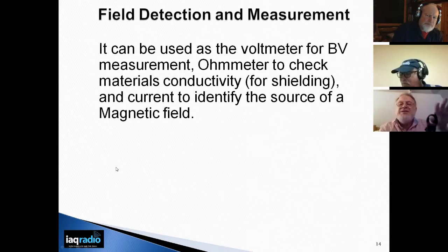So we took the meter, connected leads, and checked the electrical resistance of the screening, and the screen was definitely plastic, not metallic. Being plastic, it was of no use for shielding - if it were metallic like aluminum, it would have provided a blocking effect at the window interface.